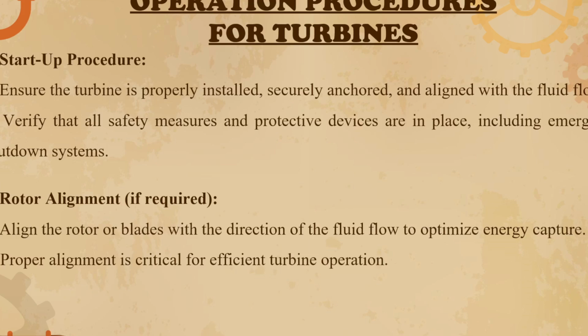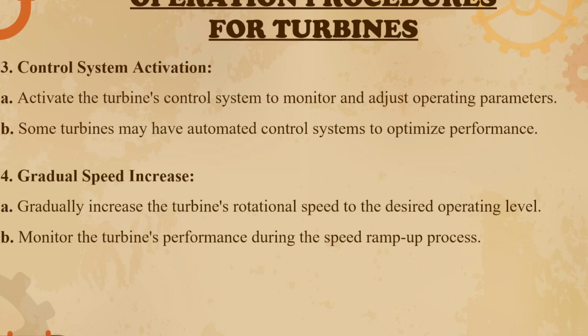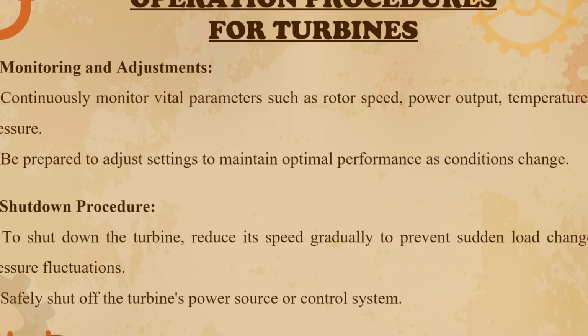For turbines, this is the last information that I will provide, which is the operation procedure. First procedure is startup procedure. Then second is the rotor alignment if required. Align the rotor blades with the direction of the fluid flow to optimize energy capture. Third is the control system activation. We must activate the turbine's control system to monitor and adjust operating parameters. Fourth is the gradual speed increase. Fifth is monitoring and adjustments. Sixth is the shutdown procedure.